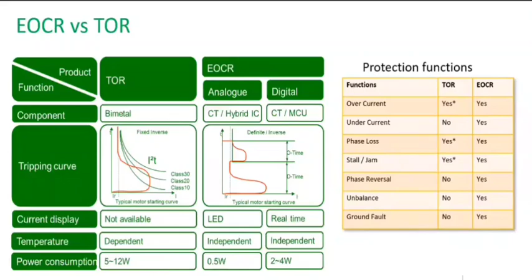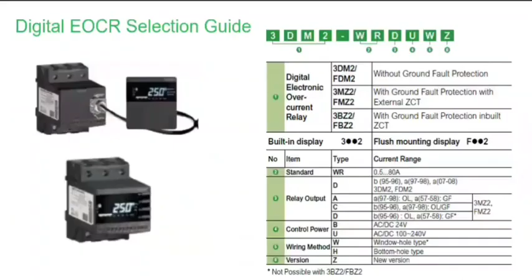Also, this product gives you a lot of benefit on inventory. How is it possible? This product is designed for 0.5 ampere to 80 ampere with its inbuilt CT. For example, all the motors available in your plant up to 37 kilowatt can be covered with the help of this single product only. Right now, if you open any manufacturer's price list, even Schneider or any competition, you will see there are thermal overload references of more than 30, 35, 40.